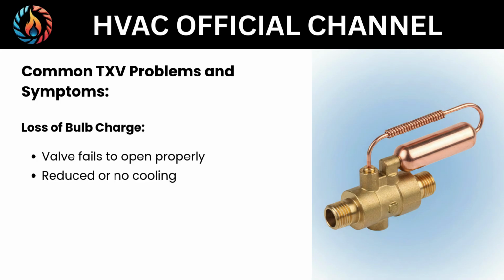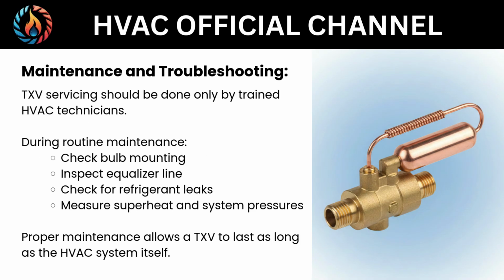Reduced or no cooling. Maintenance and troubleshooting. TXV servicing should be done only by trained HVAC technicians. During routine maintenance, check bulb mounting. Inspect equalizer line. Check for refrigerant leaks. Measure superheat and system pressures. Proper maintenance allows a TXV to last as long as the HVAC system itself.